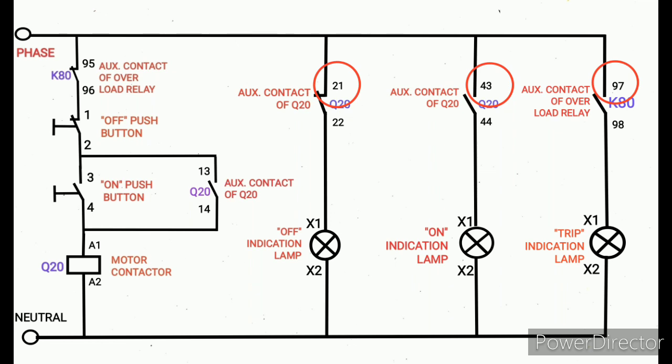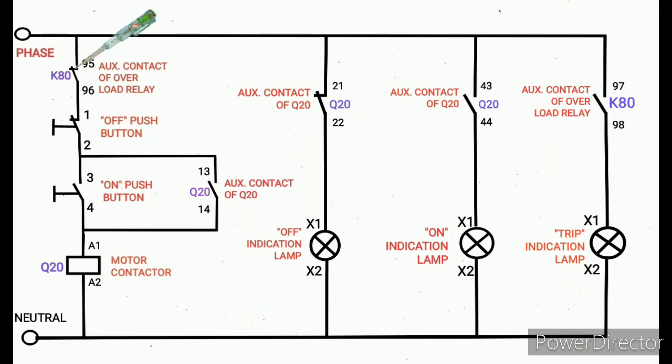Then I am going to check one by one, step by step. First, initially, the overload relay auxiliary contact K80 95. I am going to check whether the tester glows. That line is okay.